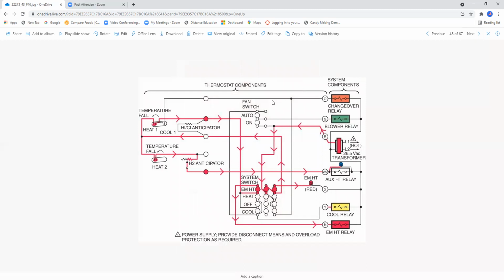Okay, another wiring diagram. Notice that you've got heat anticipators. Notice that you've got your terminals here. The E terminal is, of course, the emergency heat relay. Y is your cooling relay. X is going to energize the emergency heat pilot light. And of course, your W2 is going to be hooked up to your auxiliary heat relay, which will bring on your electric strip heat. Your transformer, interestingly enough, I do not see the common side. So this is kind of incomplete, because normally you have a common connection at the new digital thermostats in order to eliminate the battery use. Then, of course, you have the blower relay, changeover relay.